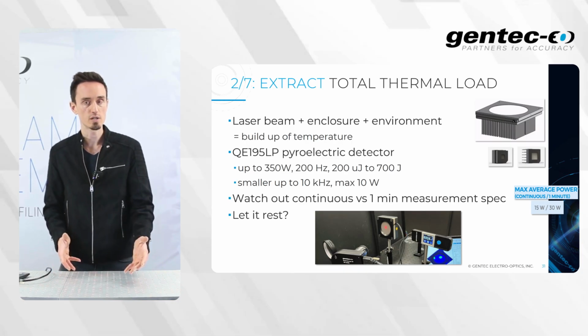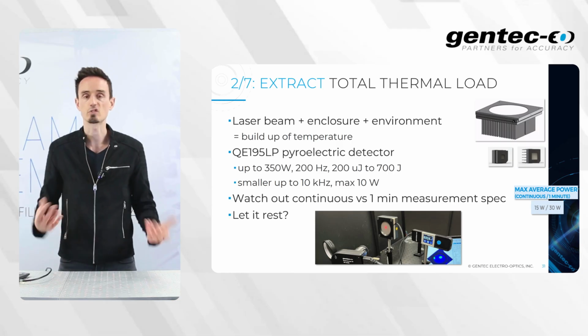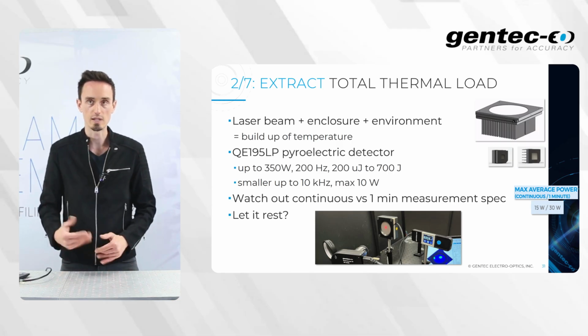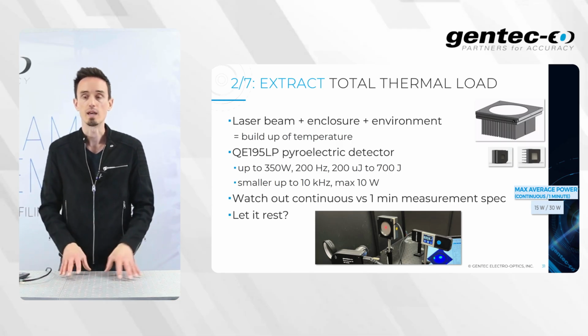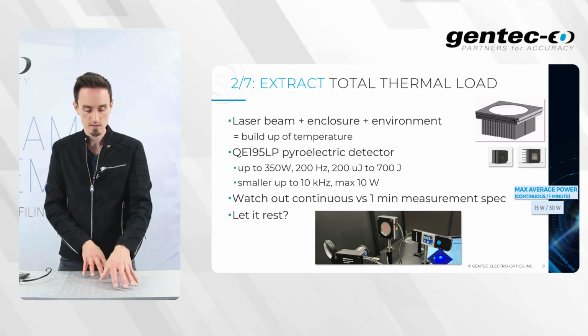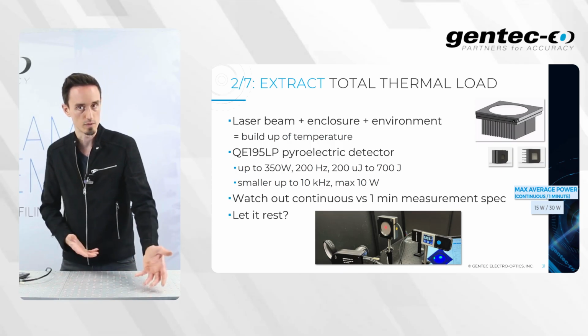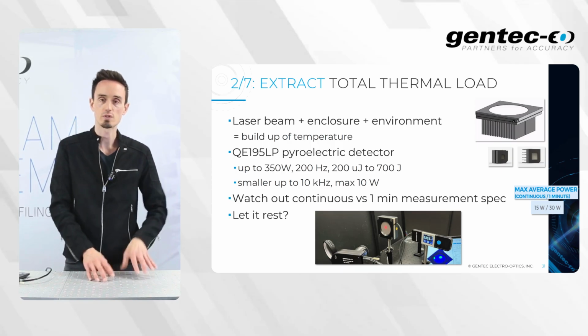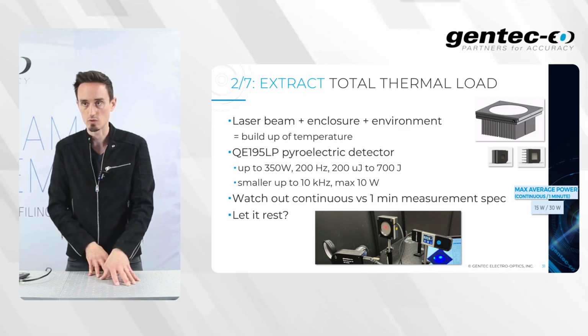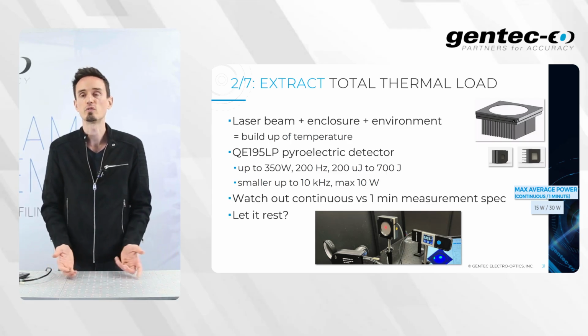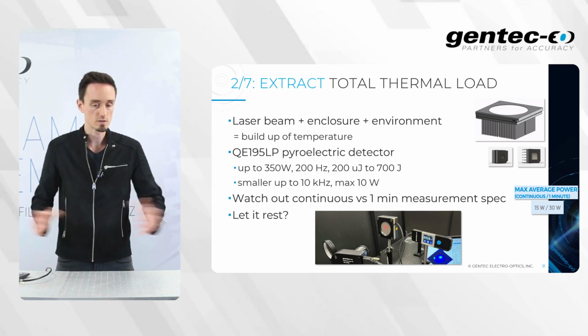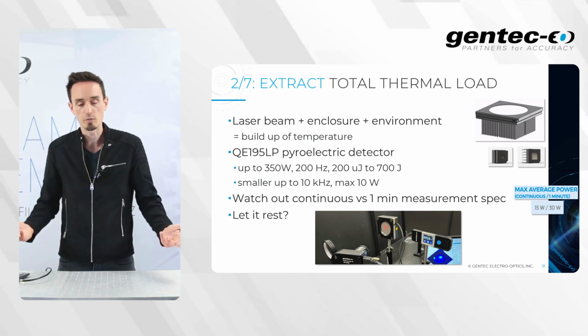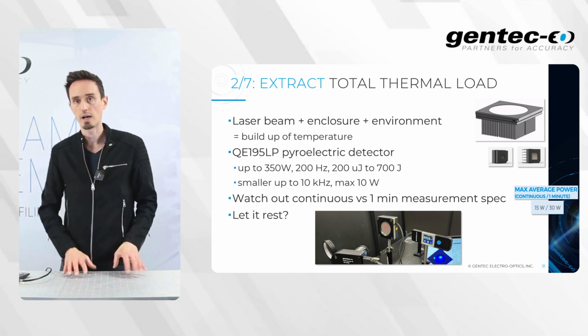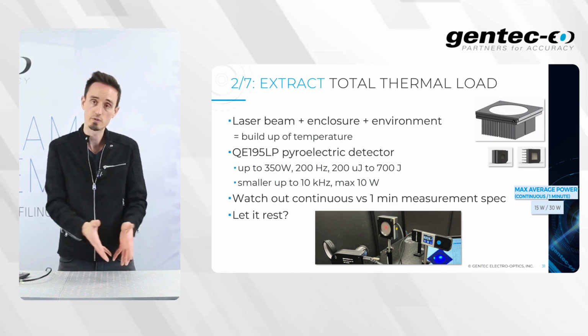Is that enough for the application? Could we build up a customized heatsink or some water lines? Do we need to adapt to that? And we need to take into consideration the duration of the measurement. Watch out for the continuous versus 1 minute measurement specification, because we do provide those specifications. If you're running continuously versus 1 minute, you could have the possibility to run at a higher power level if it's for a shorter duration.